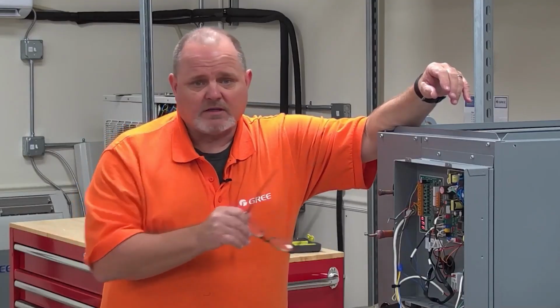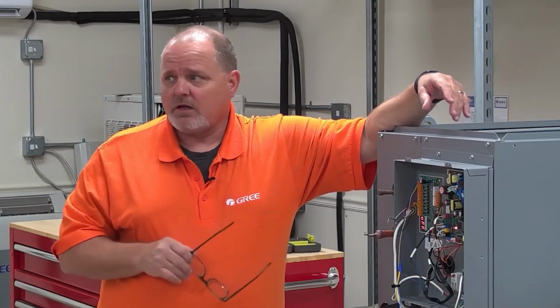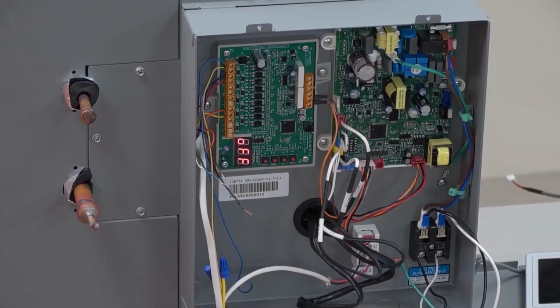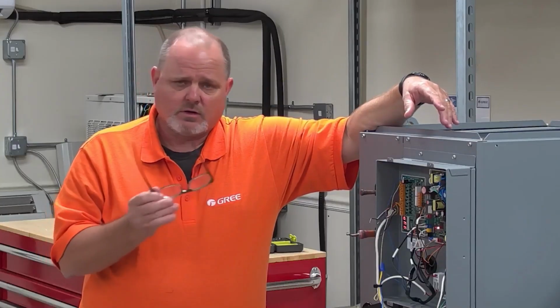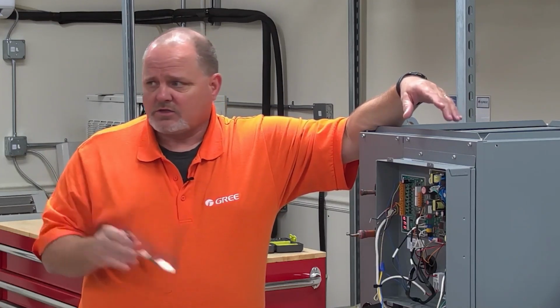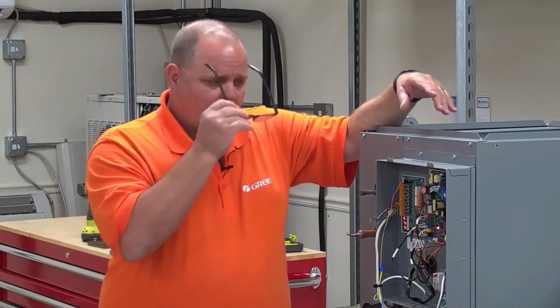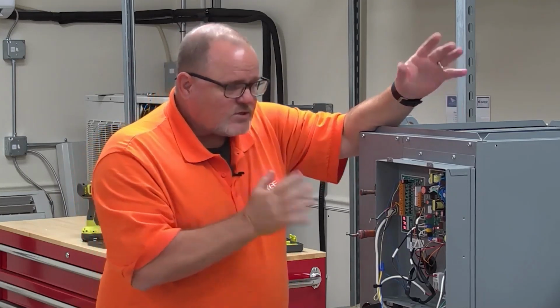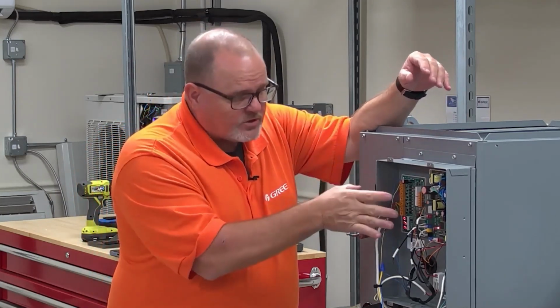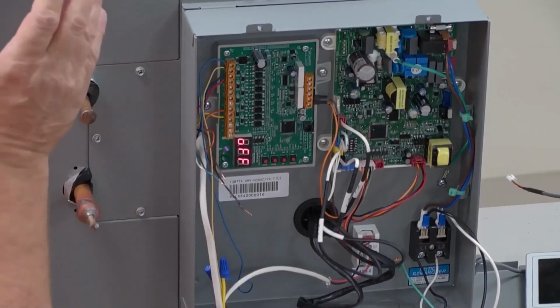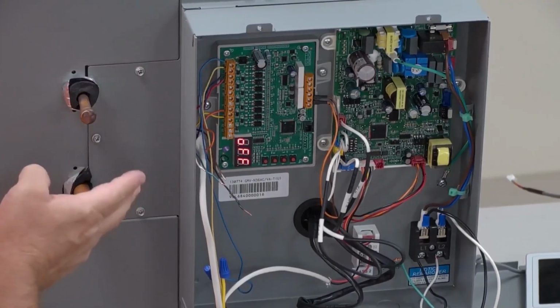So I would keep it at 00. Make sure it has no time delay because it depends on your blower. Even if your blower has a 3-minute time delay off or a 2-minute time delay off or whatever, there's really no reason to be running that heat pump anymore. Let's go ahead and when we lose that call, let's just shut it down, okay? So that's the only real settings you need to do. There is other settings that are built into it because, as I said, it is the same as the 24-volt adapter.